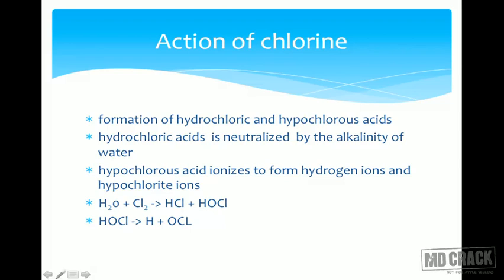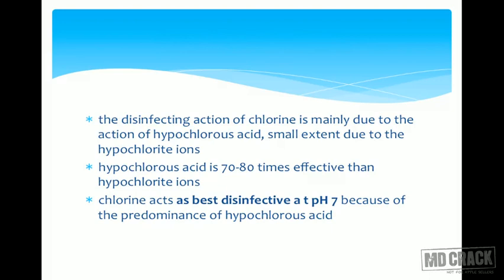Hypochlorous acid ionizes to form hydrogen ions and hypochlorite ions. These end products are less efficient; what we want is hypochlorous acid. The chemical reaction is: H₂O + Cl₂ → HCl + HOCl. The second reaction, HOCl breaking down into H⁺ and OCl⁻, is not wanted because those products are not effective in disinfection. So there is a synergy: hydrochloric acid reduces alkalinity and helps hypochlorous acid act.